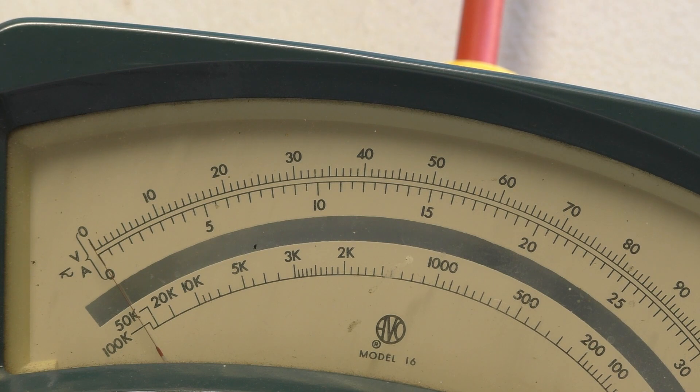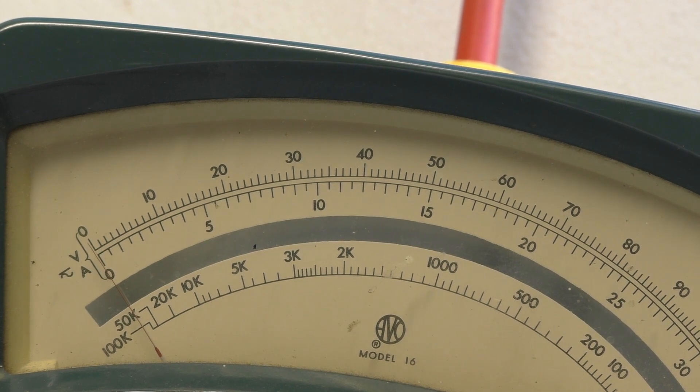As long as you have your positive side going through P1 and then S1 going to the positive side of your meter, you'll have an indication flick to the right. If the CT is wired backwards but you still had all your connections correct, then you'd know the polarity of the CT is wrong. This also helps you determine the polarity of an in-service CT if there's no markings.